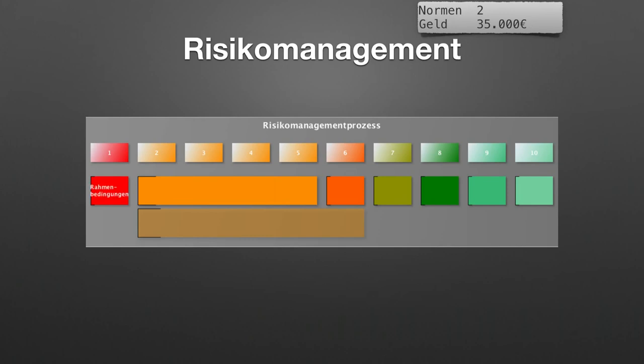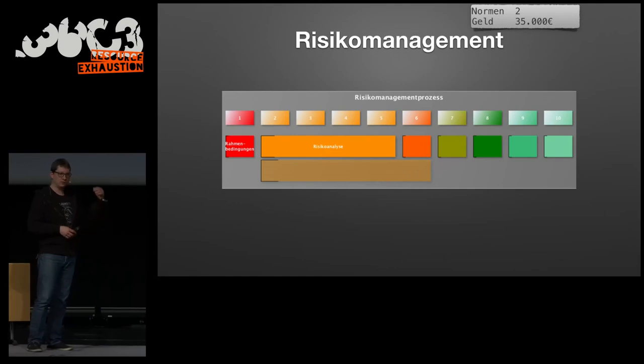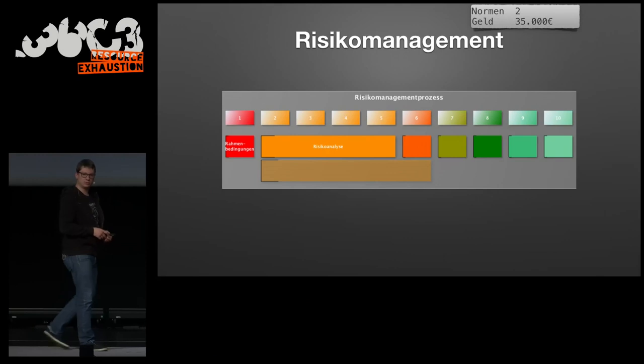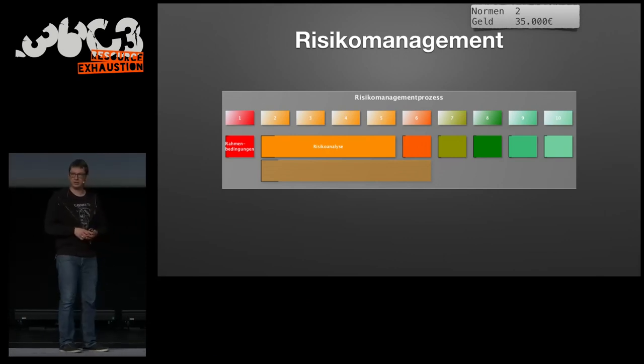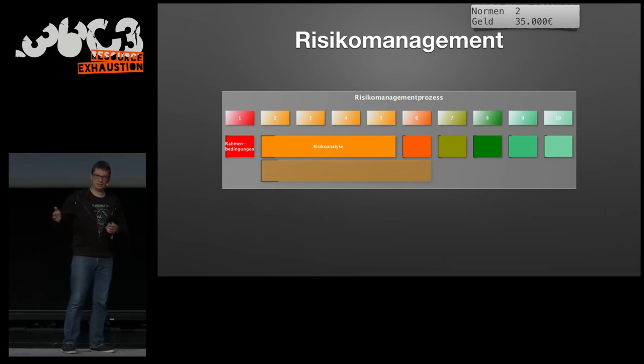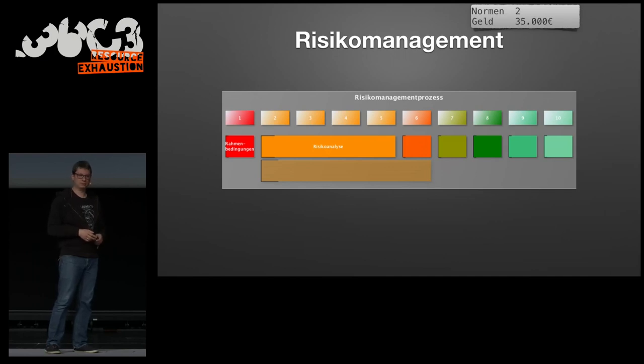The first step is, what did I write down? The edge cases. You have to determine what are the functions of the device, what risks are derived from these functions, though the standard says threats. Threats are defined as a potential source of damage. And from these threats, from events that can happen, you can go to a risk situation. So a lamp at the ceiling can fall down, but as long as no one's underneath it, it's a hazard, but not a hazardous situation. Only if people are close to it is there a hazardous situation.